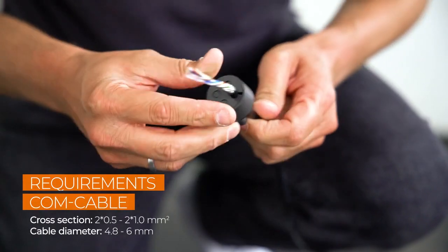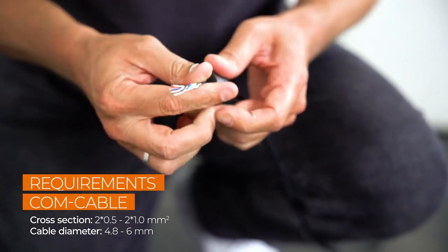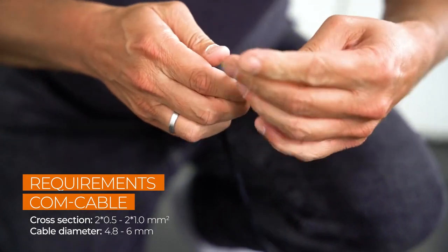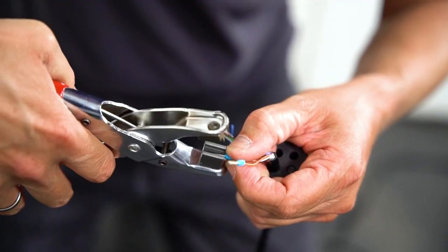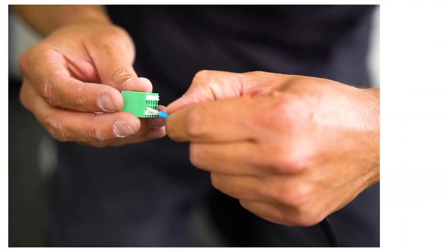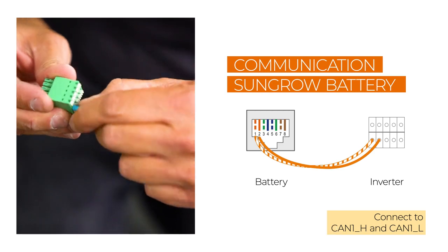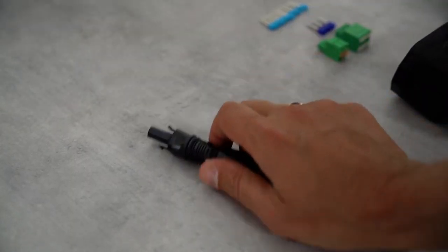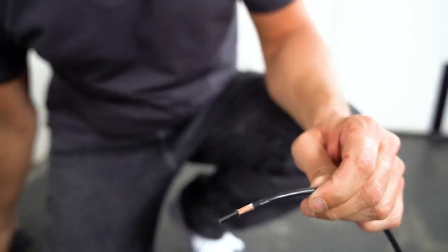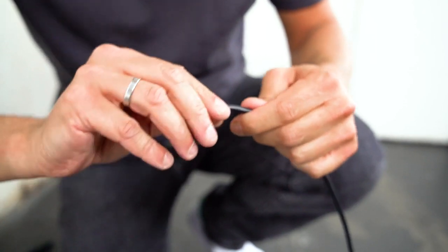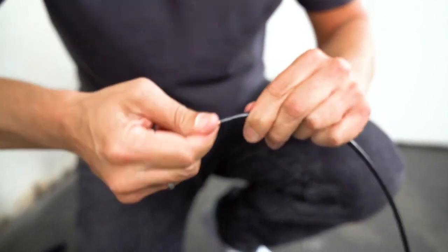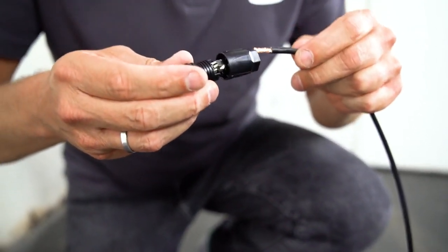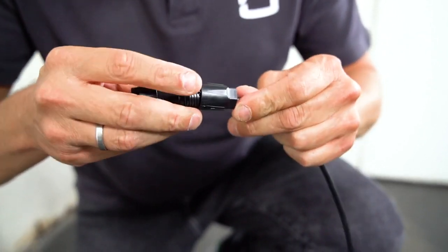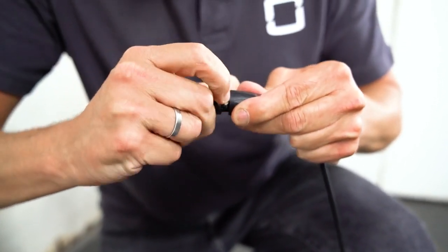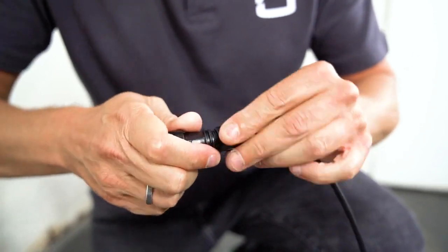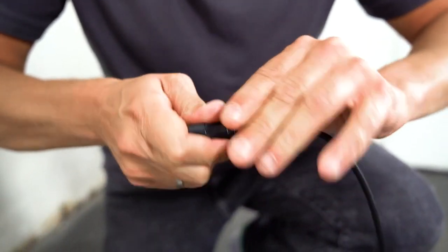Remove approximately 4 to 5 cm of the cable sheath of the communication cables. Then strip approximately 5 to 7 mm of the inner cables. Fit the cables with end sleeves before you push them into the plug. The Sungrow battery is connected to the CAN interface. In the next step, the battery will be connected to the single-phase hybrid via Sunclix connectors. Pay attention to the correct polarity. This is marked on the inverter and the battery. First, insert the cable until resistance is felt. Now, the cable is fixed to the connector by pushing down the spring. A clear click can be heard when it clicks into place. Tighten the plug. That's it.